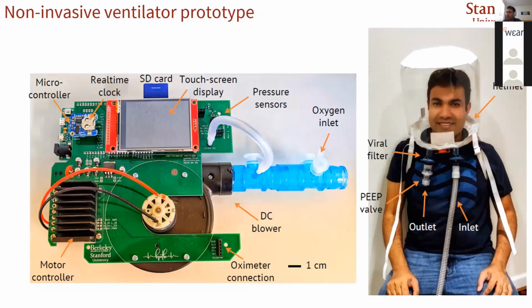And here we have the photo. Essentially, you have a microcontroller unit controlling the whole device. We have a real-time clock that maintains the time, even if it's disconnected from a power source. And then we have an SD card that records all the data. Essentially, it's like a black box for this ventilator. And then we have an easy-to-use touchscreen display. We also need to put in sensors to look at the pressure and flow. And we have the DC blower. Also, we were thinking about adding an oximeter to know the SpO2, the oxygenation of the patient. And then we have a motor controller to drive the DC blower. So this is the final product, but we had to go through 3 different designs, burning many motor controllers and also blowers to find out what actually works.